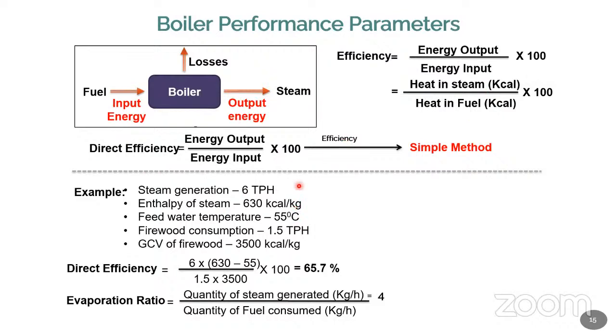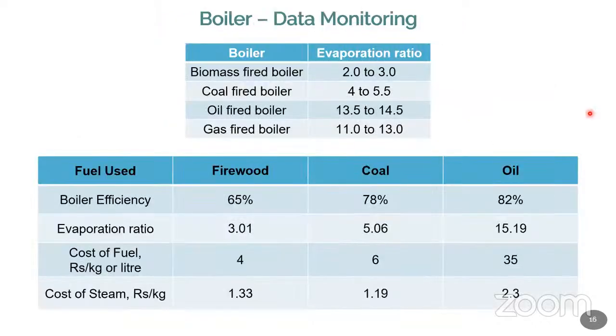There is also an indirect method, which is different. This is somewhat cumbersome, but it requires some measurements also. Normally the boiler efficiency for a wood-fired boiler is going to be around 60 to 70%, whereas a coal-fired boiler is going to be 75 to 80%. An oil-fired boiler is going to be much higher, but it requires more maintenance. Similarly, the evaporation ratio is shown like this, and the fuel cost and steam cost are also represented. This is the older value, not the newer value.